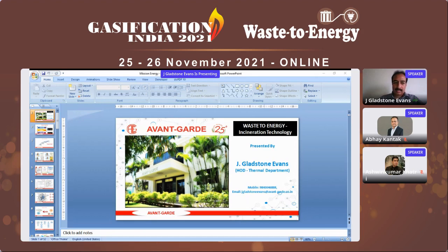So in incineration, there are three types of technology. One is moving grate technology, which is used in 90% of plants. And you have fluidized bed boiler technology, which you cannot use for direct dumping of the waste. When you segregate the waste, convert it to RDF and make the RDF into a particular size, then fluidized bed technology can be used. Mainly, this is used for co-firing in a power plant where they use coal. A certain percentage of coal can be offset by using RDF in the fluidized bed boiler. But 100% firing of RDF in the fluidized bed boiler is not very successful. Then you have rotary kiln technology, which is mainly used for hazardous or hospital waste incineration.